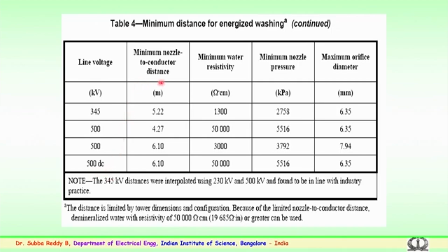given here. So, you can see here again the minimum nozzle to conductor distance has to be maintained in meters. This is the minimum water resistivity which has to be done. Above 400 kV the water resistivity changes, and here you see the minimum nozzle pressure changes after 400 kV or 345 kV. Further there is a change in the pressure and also the maximum orifice diameter changes depending upon the voltage level and the surface conditions. So, point to be noted here, up to 345 kV distances were generally interpolated using a 230 kV and 500 kV and are found to be in line with the industry practice. So, most of this the feedback which have been taken from the industry, the guidelines have been set for cleaning.